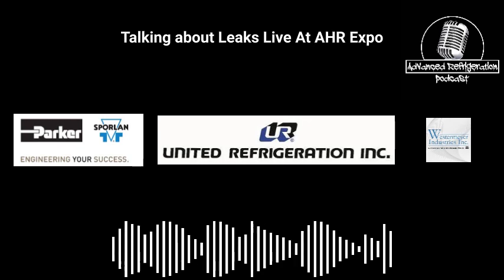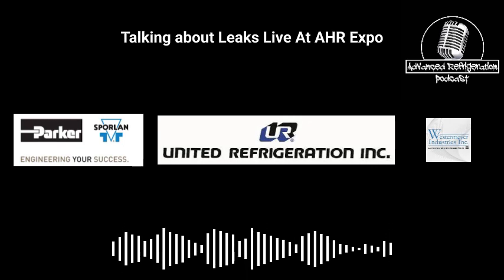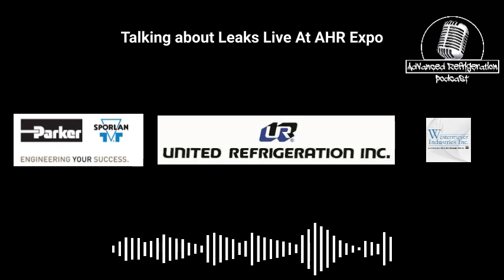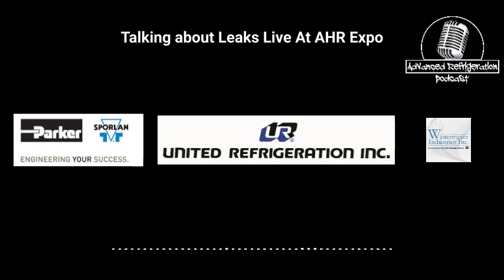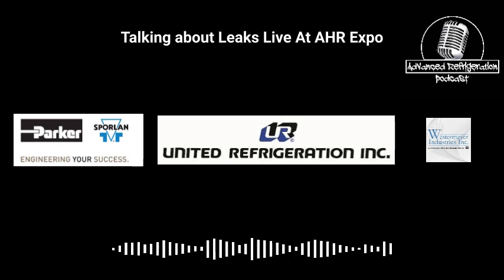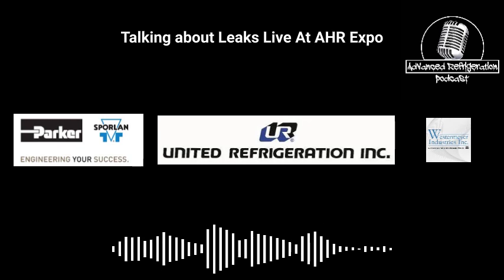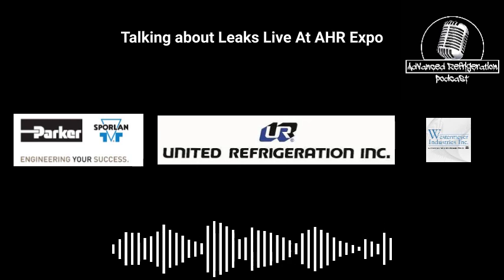So hold on, when you say crack lines, are you talking vertical or horizontal, like where it's actually going through with the flow of the pipe? Or? It doesn't matter. It's either or. Okay. So what ends up being is VFDs and compressors, especially recip compressors, they get a harmonic induced vibration.